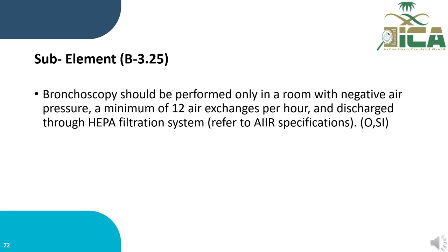B3.25, bronchoscopy should be performed only in a room with negative air pressure, a minimum of 12 air exchanges per hour, and discharged through a HEPA filter system. Refer to the airborne infection isolation room specification. For this sub-element, we need observation and staff interview.